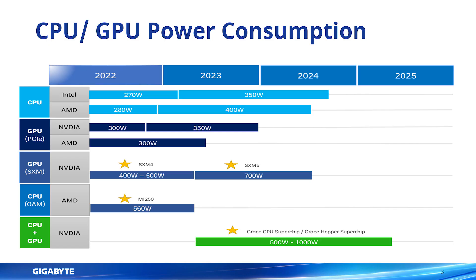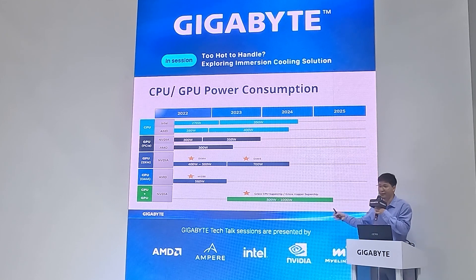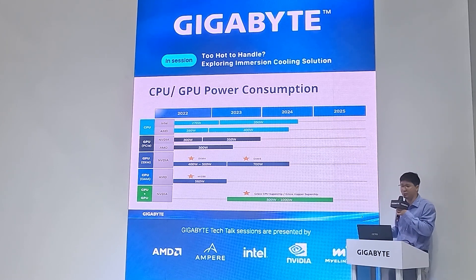Looking at this GPU and CPU power consumption table, for last-generation CPUs — Intel Whitley and AMD Milan — the TDP was 270 to 280 watts. This generation, Genoa and Sapphire Rapids, has reached 350 to 400 watts. For GPUs, the A100 was 400–500 watts in 2022, and the H100 is 700 watts in 2023. We can see a clear escalation of power consumption year by year.